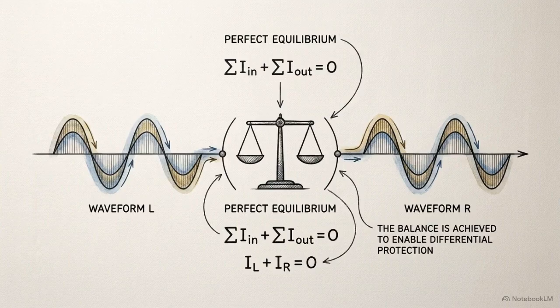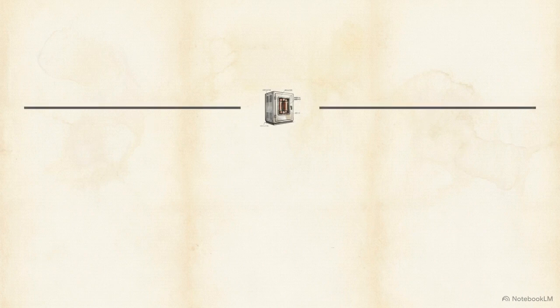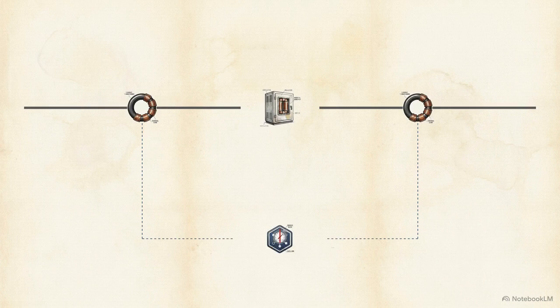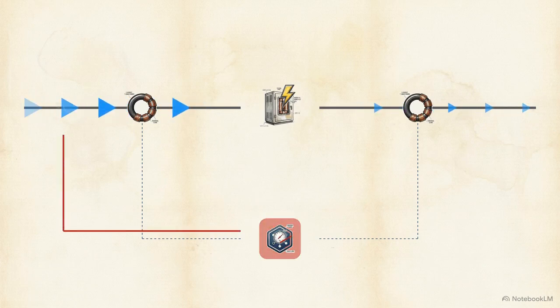This is differential protection. It is a logic system based entirely on real-time current comparison. This schematic shows how we place current transformers on both the primary and secondary sides of the unit. During normal operation, the differential relay continuously compares measurements from both sides, verifying they balance to exactly zero. If an internal winding fault occurs, current leaks within the system, instantly shifting that balance out of equilibrium. The differential relay detects this localized imbalance and immediately triggers a trip signal to the circuit breaker.